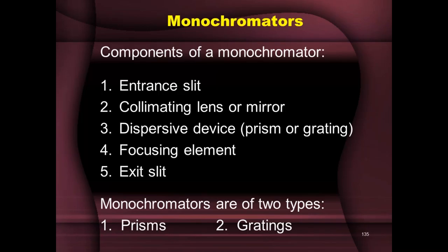Then you have a focusing element — a lens or a mirror — which converges the radiation onto a focal plane that has an exit slit. The fifth component is the exit slit on the focal plane. Through the exit slit, the radiation exits out of the monochromator and is naturally incident on the next component, which is the sample cell containing the sample.